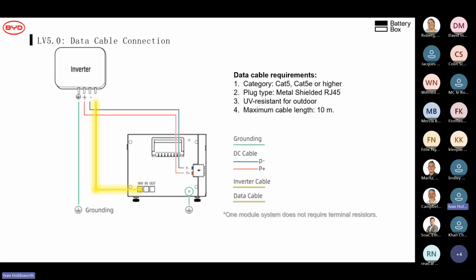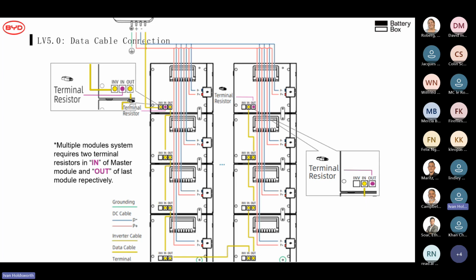And here we can see a single battery connected to your inverter: your positive and negative power connections, your inverter comms, and your earth, your grounding. Grounding is always very important for the stability of the communications. And here we can see how to connect multiple batteries in parallel. It's very important to get your cables in the correct position because the batteries are automatically configuring. So if your cables are all in the correct position, you don't have to use an app or anything to commission the batteries.